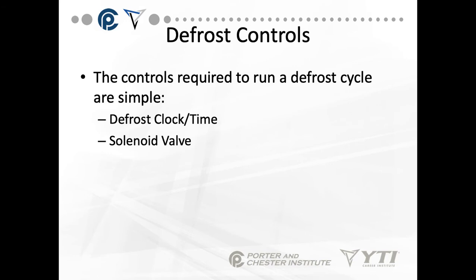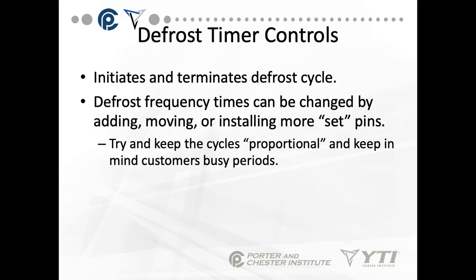The controls required to run a defrost cycle are simple: a defrost clock or timer and a solenoid valve in the case of hot gas defrost. The defrost timer control initiates and terminates the defrost cycle. The defrost frequency times can be changed by adding, moving, or installing more set pins, or in the case of digital clocks, just more set points.